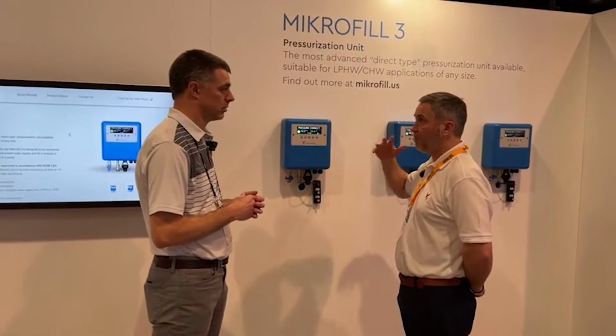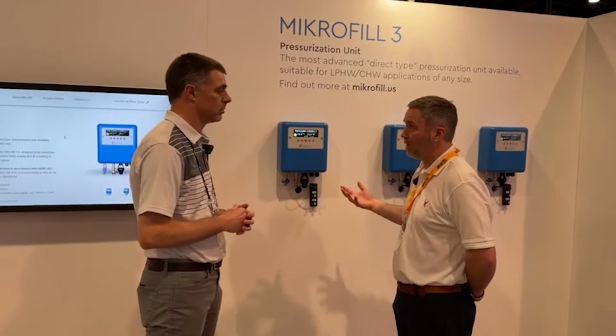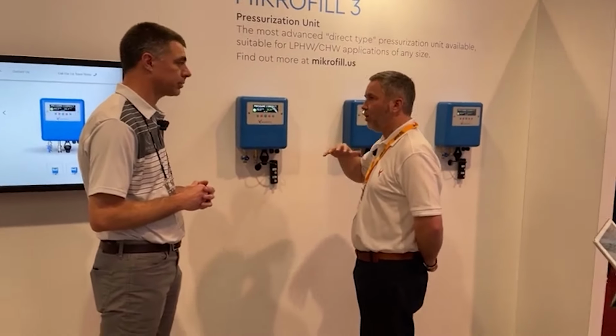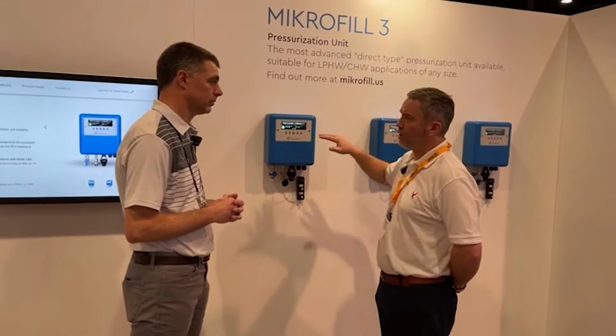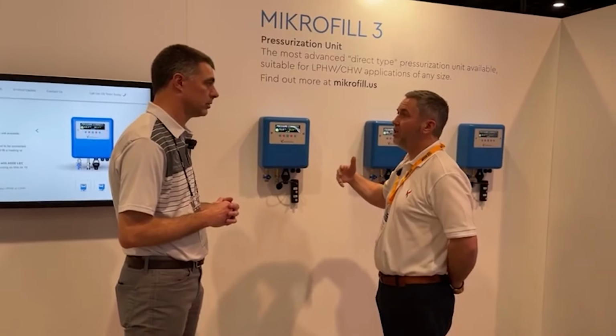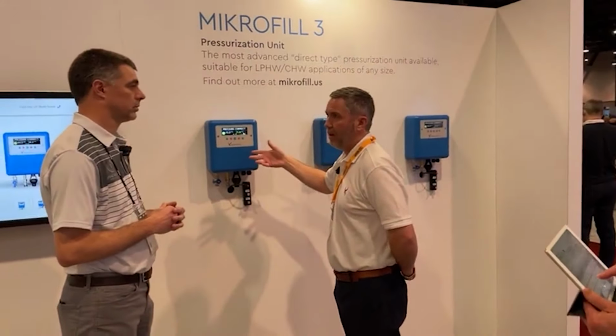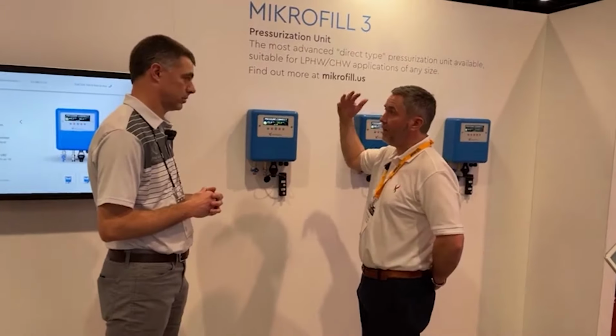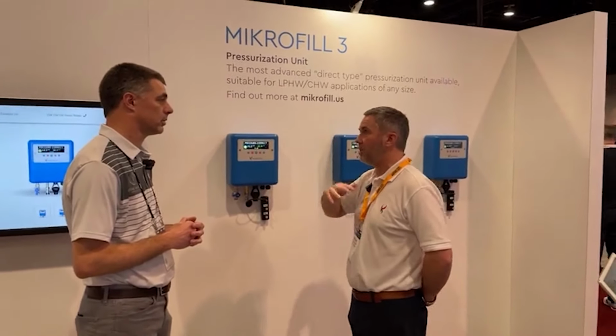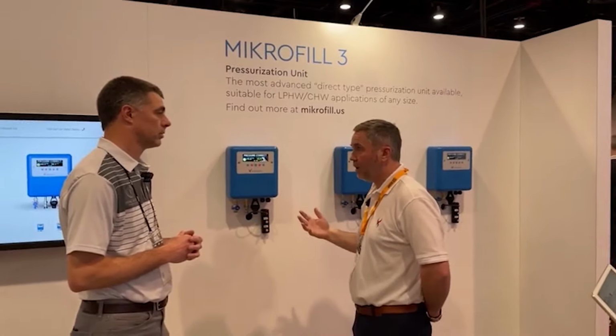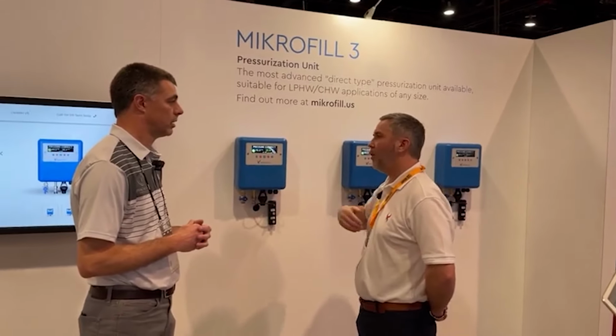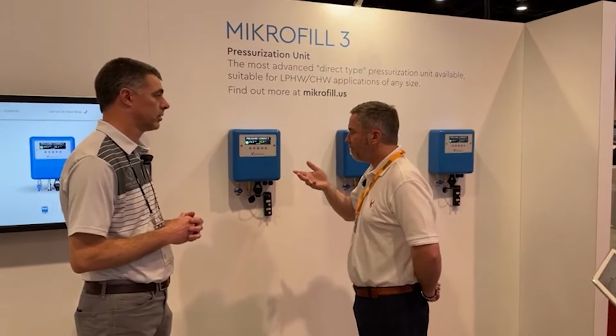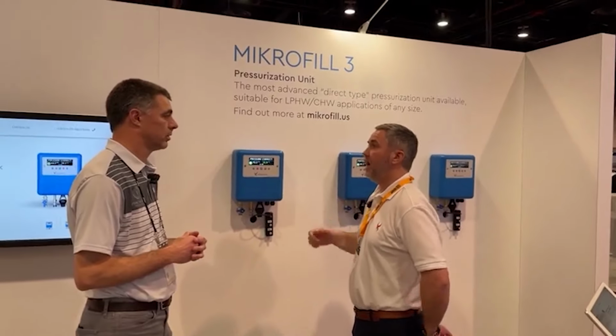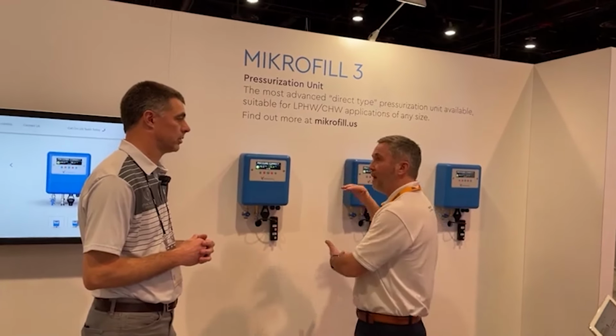So you need an expansion vessel or a tank or tanks with it. Okay. So the air cushion or nitrogen cushion charge needs to match the cold fill setting. On a heating circuit, if you have 30 psi on the cold fill, which is the highest point of that heating or chill circuit, you have 30 psi in the air cushion on the bladder of the tank. Yeah. On heating, through the elevation of temperature, the pressure increases, and the tank is there to absorb that volumetric expansion.